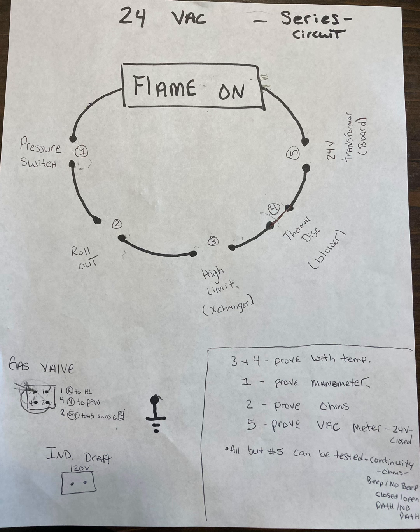It can also be tested and proved with the power on using the hopscotch method. One lead lands on the ground and the free hand comes into it and comes out of it. Do I have it there, and do I have it there? And we can also test a pressure switch, is it open or closed, using continuity. Do we have a path, or is there not a path? Is there a beep or no beep?